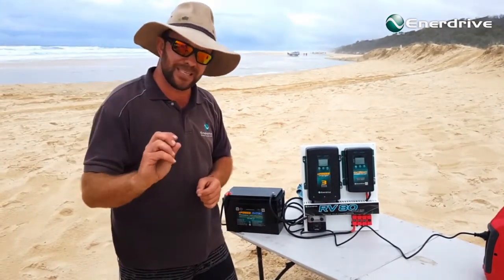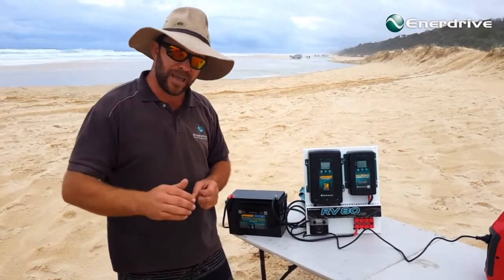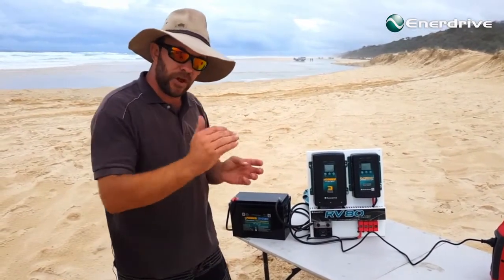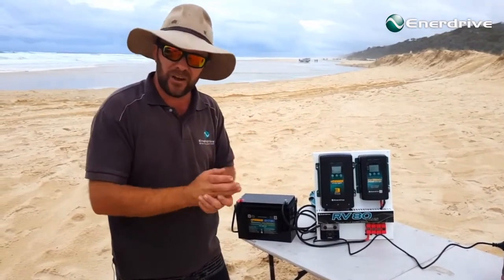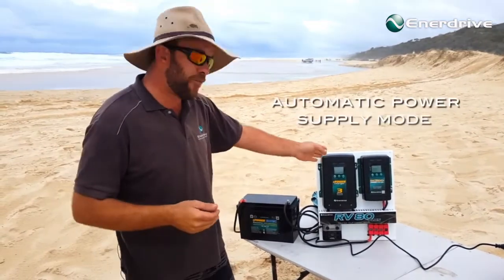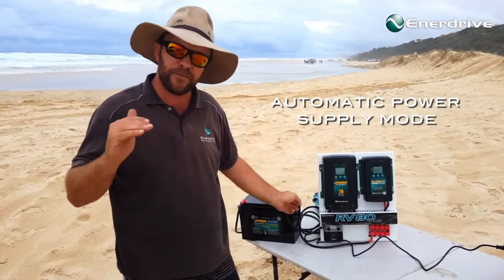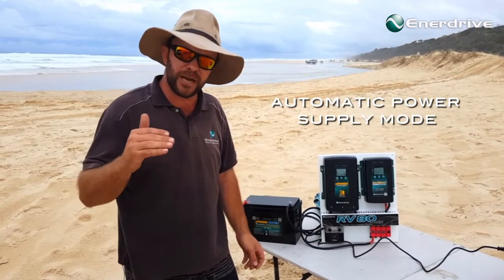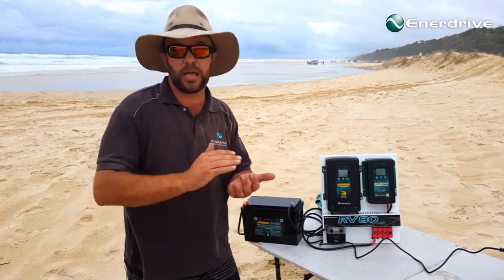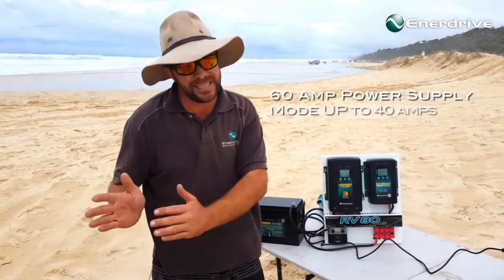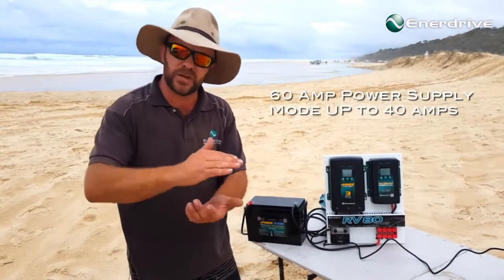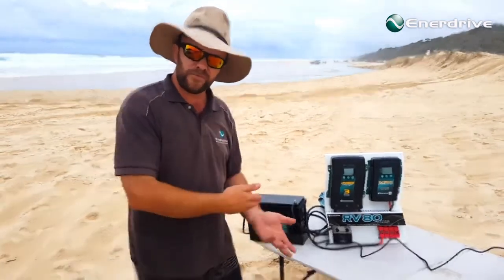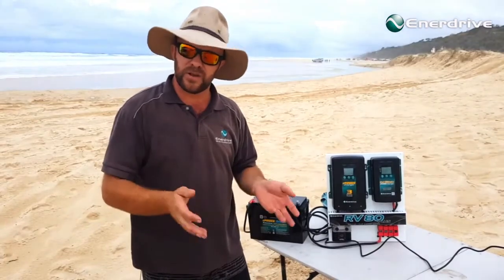And that brings me to the next point, power supply. When this charger gets to float mode, it will support any load up to its rating. This is a 40 amp charger - it will remain in float and support a load coming out of your battery up to 40 amps, up to 20 amps for the 20 amp charger. The 60 amp charger will support a load up to 40 amps, and likewise our 24 volt chargers will support a load up to 30 amps as well.